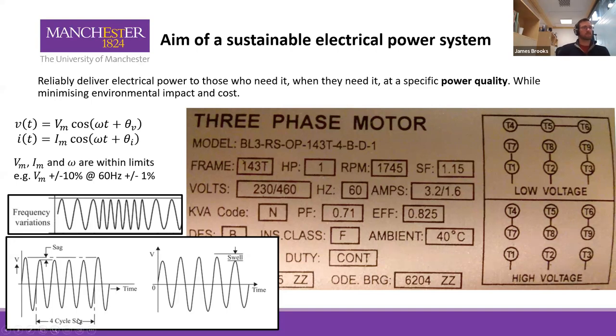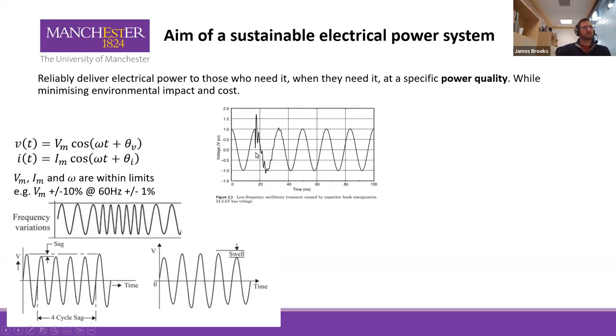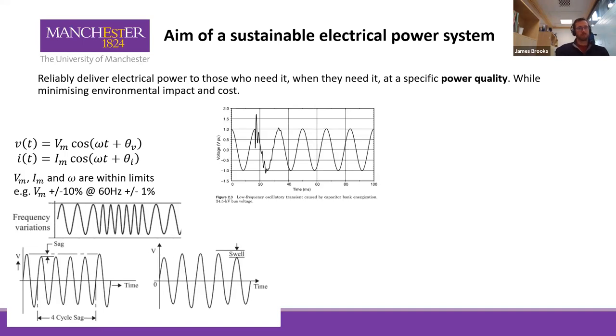A four-cycle voltage sag only lasts a short period of time. Then there are transients — events that occur and decay back to zero. This particular one was a capacitor bank energisation: it switches on, energises, causes the voltage to fluctuate and oscillate, then after one-and-a-bit cycles it settles back down. That voltage goes up to a 60% increase, which is far outside the 10% bound, but it may be acceptable because it's over a very short period of time.